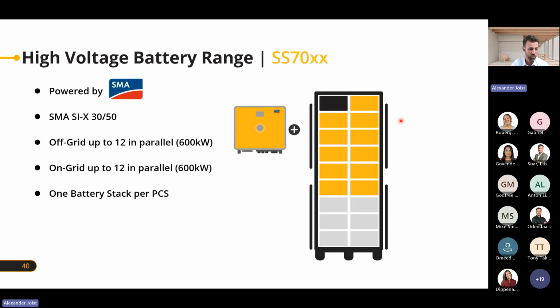If you look into that a little bit more in detail, we can see the new SMA Sunny Island is for 12 pieces in parallel, so up to 600 kilowatts on-grid or off-grid. That doesn't matter. So there's no limitation of that, but 12 is the maximum for on-grid or off-grid operation of the Sunny Island.